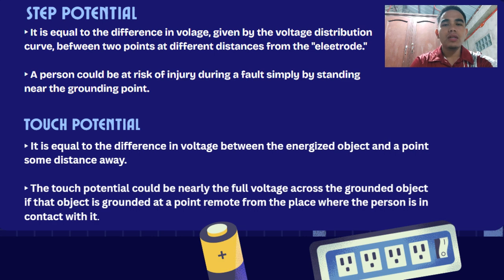So, step potential. Step potential is equal to the difference in voltage, given by the voltage distribution curve, between two points at different distances from the electrode. A person could be at risk of injury during a fault simply by standing at or near the grounding point. So, touch potential. Touch potential is equal to the difference in voltage between the energized object and a point some distance away. The touch potential could be nearly the full voltage across the grounded object if that object is grounded at a point remote from the place where the person is in contact with it.